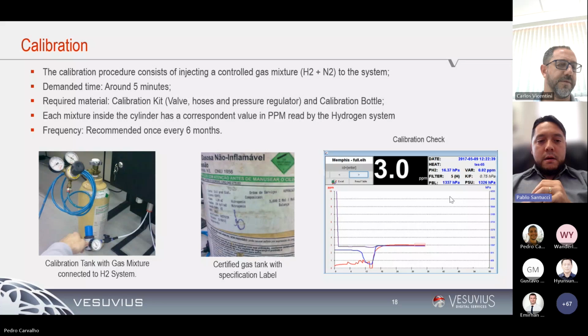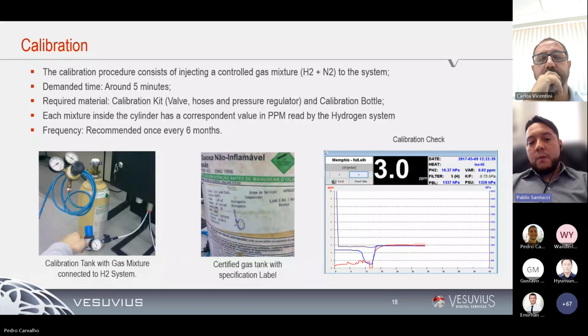So this is not, say, a demanding or tough procedure. It takes around 5 or 10 minutes, depending on where the equipment is located. In addition to that, we consider calibration gas for running this calibration procedure, which is a mixture of gas with X amount of hydrogen in nitrogen balance. For example, in this case, as you can see in the graph, 3.0 ppm dissolved hydrogen in steel means that our calibration gas used for reaching that number, 3.0, was 1.5% hydrogen in a nitrogen balance bottle.